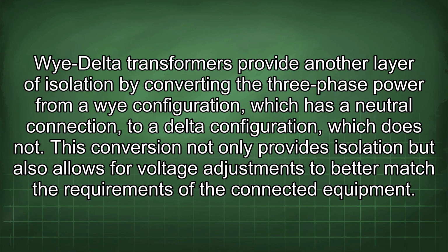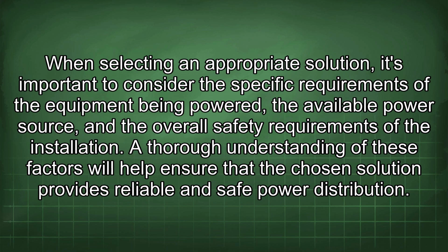Wye-delta transformers provide another layer of isolation by converting the three-phase power from a Y configuration, which has a neutral connection, to a delta configuration, which does not. This conversion not only provides isolation, but also allows for voltage adjustments to better match the requirements of the connected equipment. When selecting an appropriate solution, it's important to consider the specific requirements of the equipment being powered, the available power source, and the overall safety requirements of the installation. A thorough understanding of these factors will help ensure that the chosen solution provides reliable and safe power distribution.